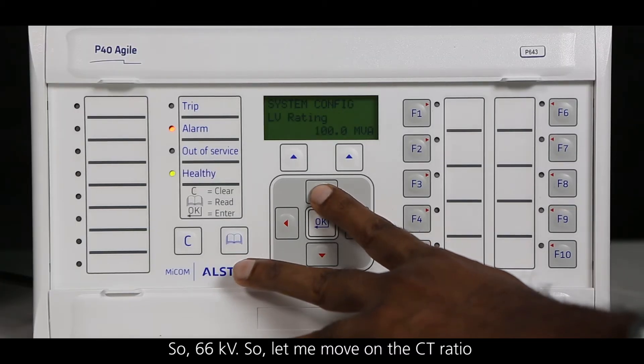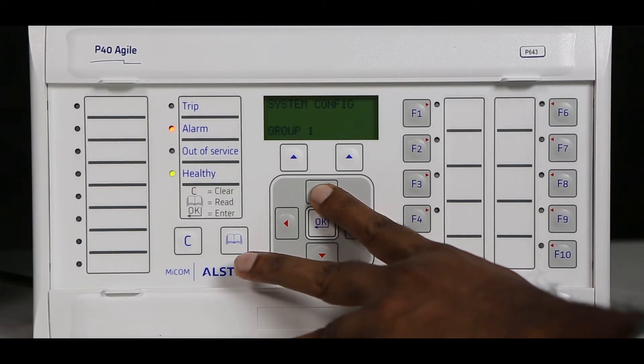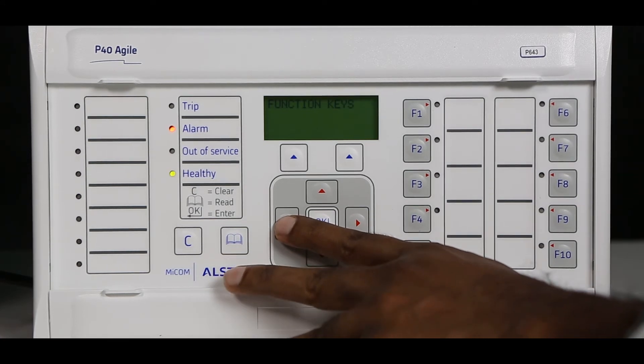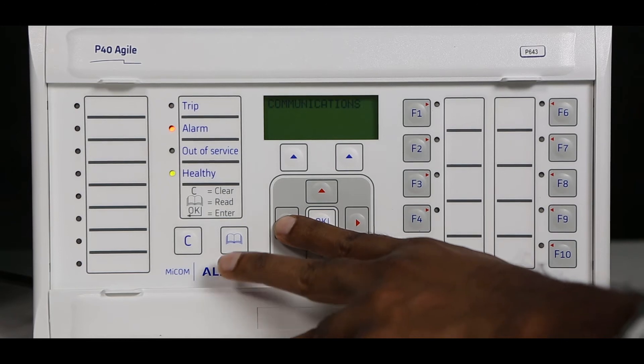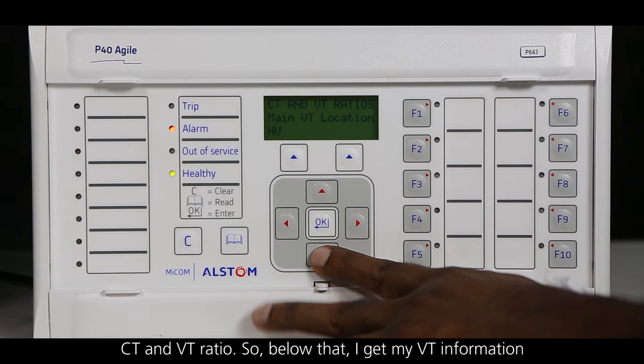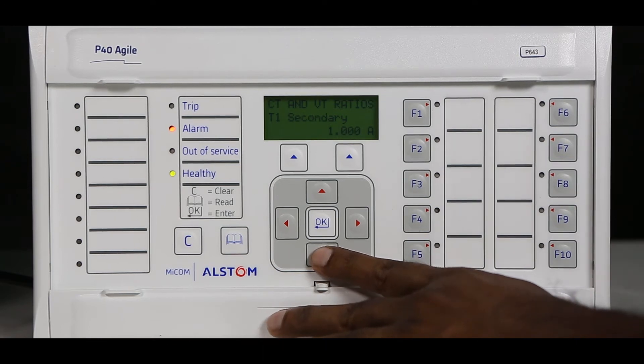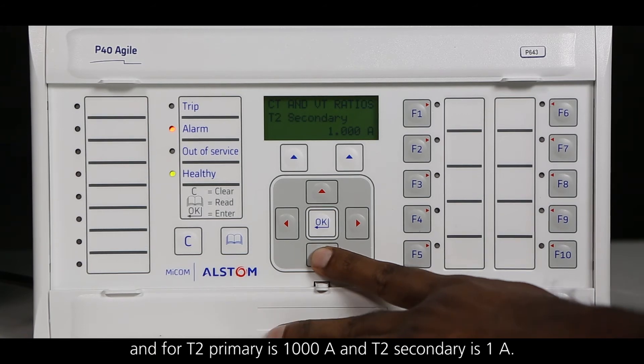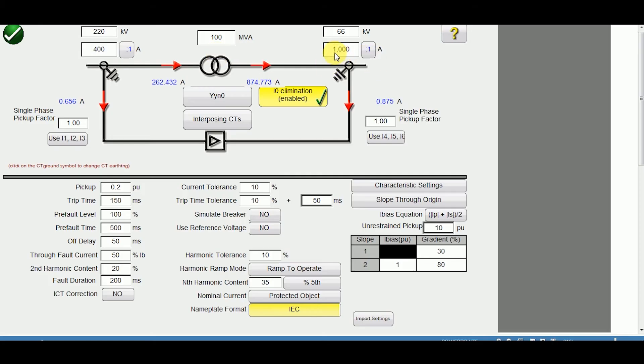Now let me move on to the CT ratio and VT ratio. Below that I get my CT information. CT T1 is 400 bar 1 amp, and T2 is 1000 bar 1 amp. My vector group is Yn, Yn 0 as seen earlier.